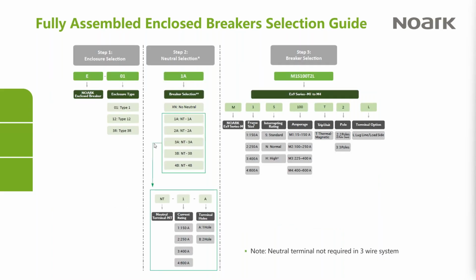All right, so that's the 1200 amp. I'm going to move now into the selection process for enclosed breakers. The first step is selecting the enclosure, and the catalog number nomenclature starts with an E for enclosed breaker, and then the next digits indicate the enclosure type. So 01 is a type 1, 12 and 3R, those are pretty obvious. Then the next step is whether you're going to use a neutral or not. Neutral is required specifically for service entrance, but also for many other applications where the neutral connection in a 3-phase 4-wire system needs to come through to the parts of the power system below this breaker.